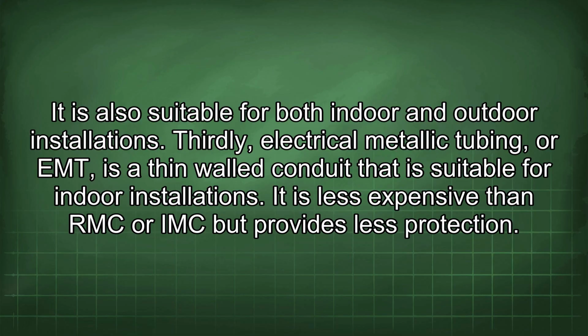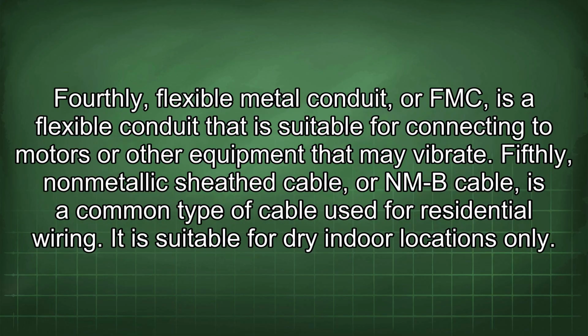Thirdly, electrical metallic tubing, or EMT, is a thin-walled conduit that is suitable for indoor installations. It is less expensive than RMC or IMC but provides less protection. Fourthly, flexible metal conduit, or FMC, is a flexible conduit that is suitable for connecting to motors or other equipment that may vibrate. Fifthly, non-metallic sheathed cable, or NMB cable, is a common type of cable used for residential wiring. It is suitable for dry indoor locations only.